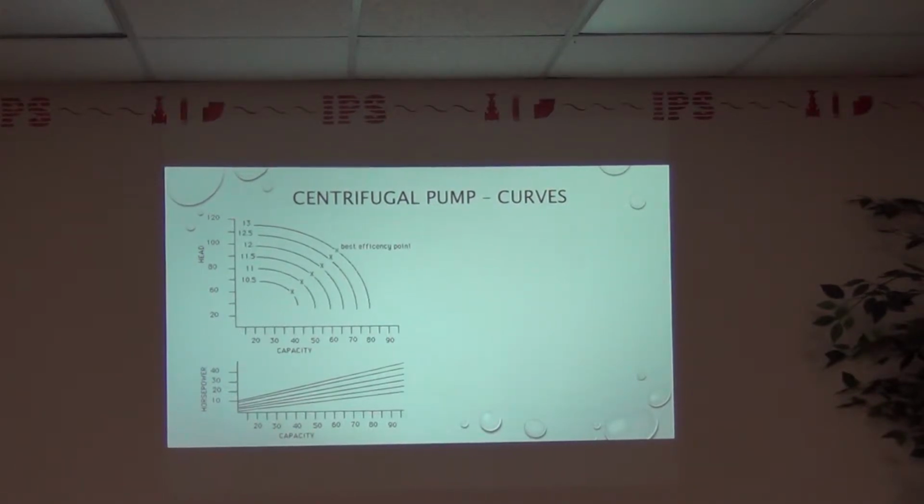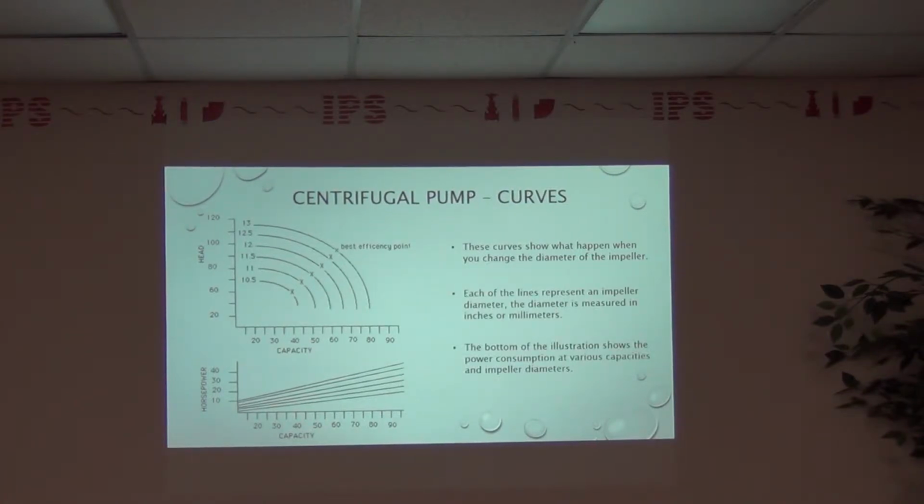So in that case, it would be something like a 7.5 horsepower with a 10.5 inch impeller trim. When they trim the impeller, that doesn't do anything to the housing itself. It's an open area. Basically, 5 years ago the guy's requirement was 500 gallons a minute. Now he needs 1,000 gallons a minute. Just swap out the impeller and horsepower? Well, everything else comes into it.